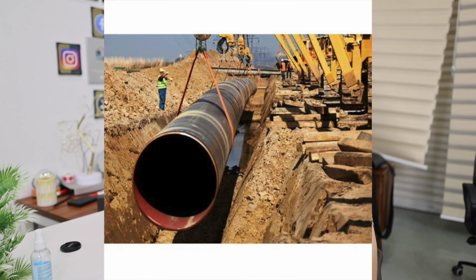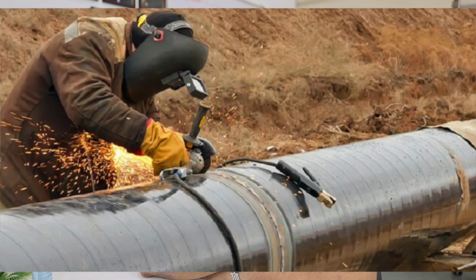How is the welding of chilled water pipe tested? It's a very important question. There are two types of piping systems, the small piping system and the big piping system. For the small piping system, for example, if you are putting a 2 inch pipe or 3 inch pipe, you can directly put water and test it, no problem. But if it is a 6-inch pipe, 8-inch pipe, and its length is more than 50 meter, 100 meter, 200 meter, whatever it is, when you are filling the water, a leak is found. Again, you need to drain the water. So that much volume of water you cannot handle.